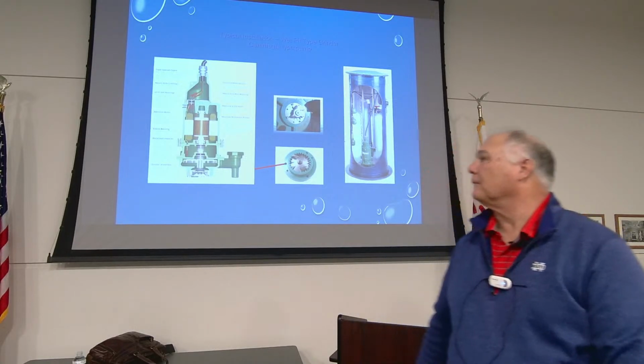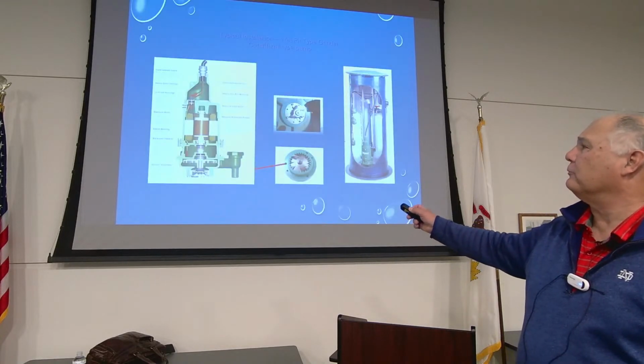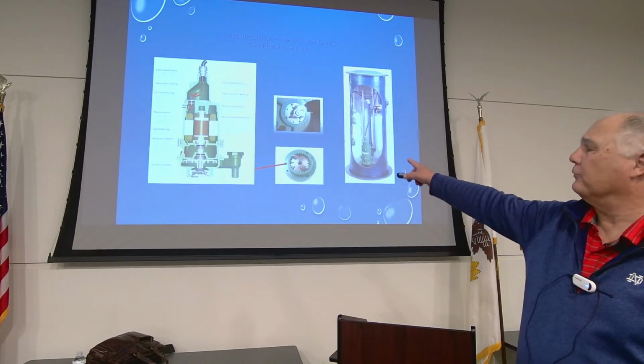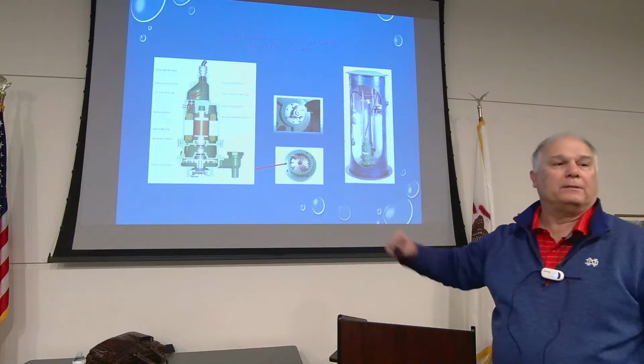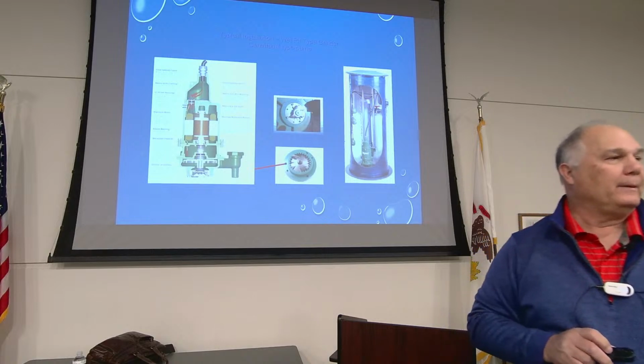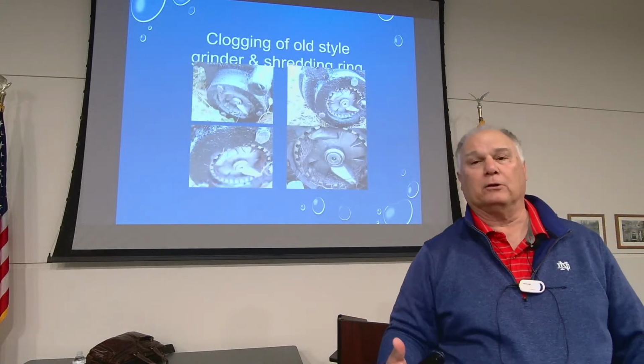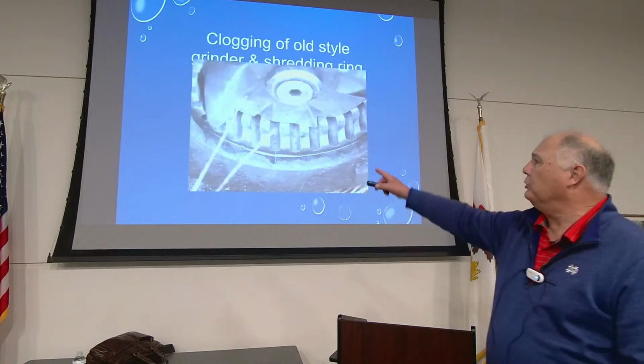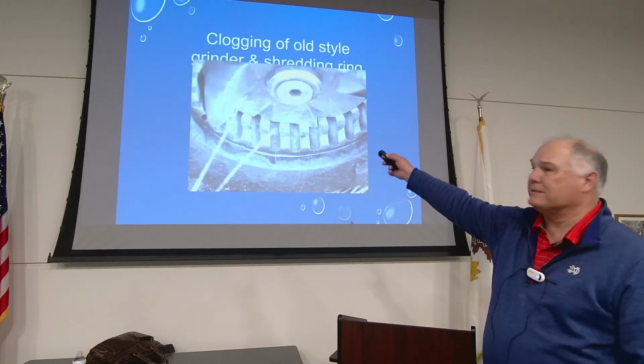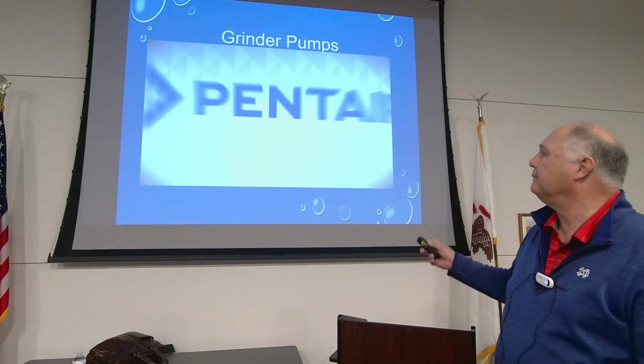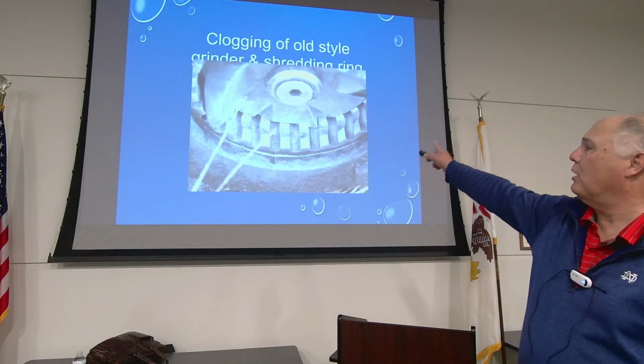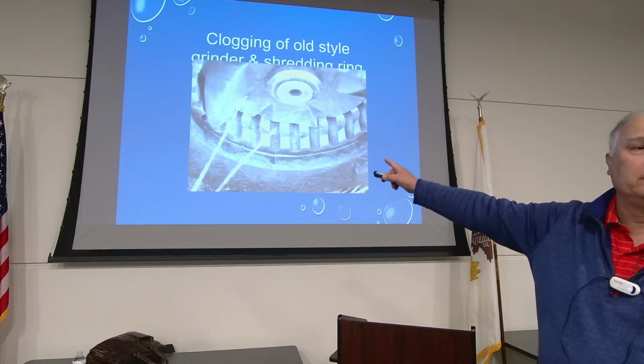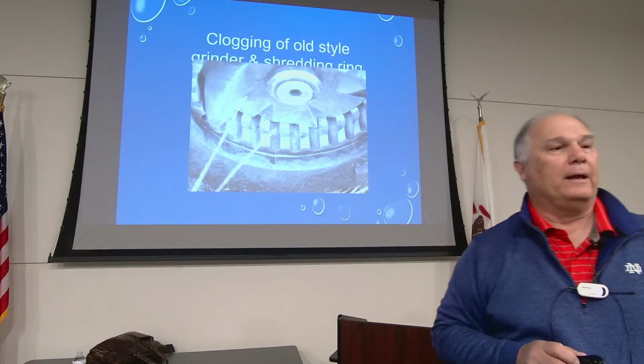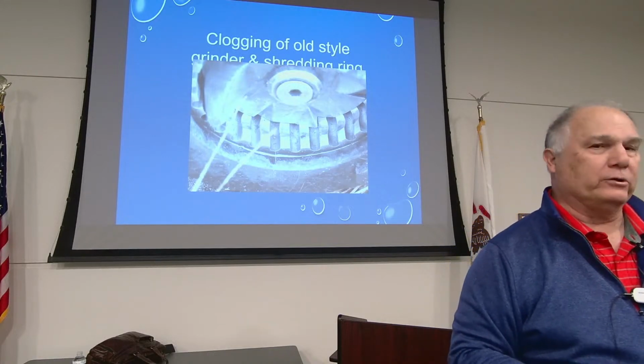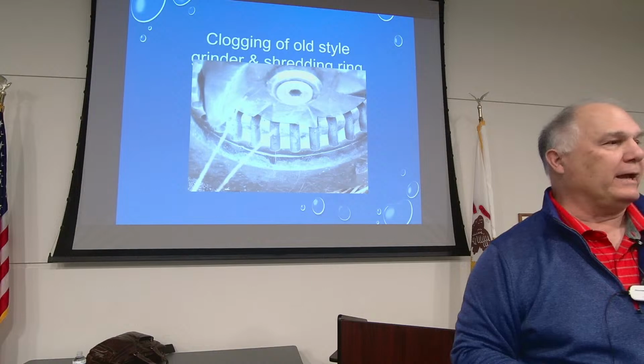Okay? So grinder pumps, there's a couple different ways to do grinder pumps. There's an old style of grinder shredding ring, which is the bottom. Then there's a new slicer dicer, which is the top. The new slicer dicer is a much better product than the old one, because what happens with the old one, you get material like this, the grinder shredding ring. This has been installed at a dog pound for a week. You can see how much it has gone and routed out the side of the shredding ring, and it's just worn out. And a grinder pump requires that torque to get operational so it can operate and cut that material that might be stuck halfway in and halfway out.